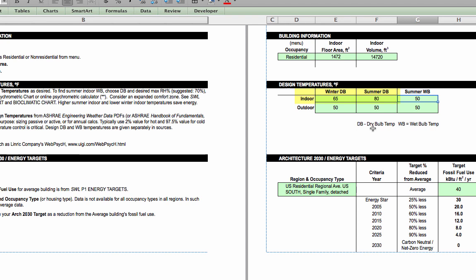Now, if you choose a narrower comfort range, which is more common in non-passive buildings, then the building systems would have to be larger and the mechanical systems would run more hours, and in a passive building, the passive systems themselves would have to be larger. So it turns out indoor temperatures are actually one of the biggest choices that you have in affecting energy use.